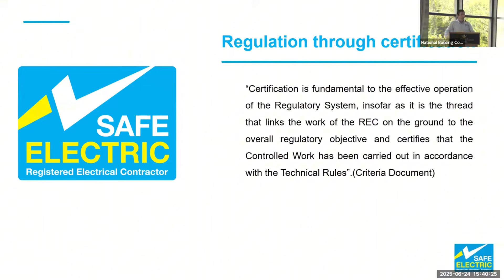They will also check varying test results. We have them trained to look for what we'd see as obvious mistakes on the certificate - they look for the lowest resistance of protective conductor and the highest insulation resistance. These things are a giveaway to inspectors, letting us know if the installation has actually been tested in accordance with the wiring rules. We're quite clued in, we can see when someone hasn't in fact tested the installation. If they haven't, it's given to an inspector - we'll either go out and inspect the job, or they get a phone call from us and we'll have a serious word with them.